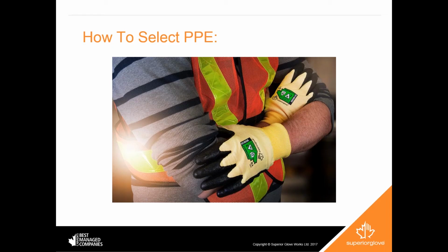So if you don't take anything away but that, remember that an arc flash glove is never going to protect against a shock. The reverse of that would be that if you are wearing rubber insulated gloves and the leather protectors to protect against shock, you can also be protecting against arc flash at that point, but not in the reverse.